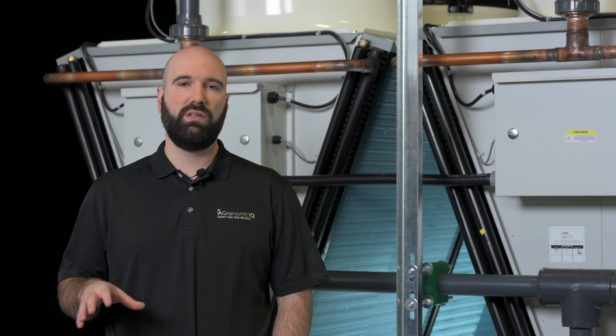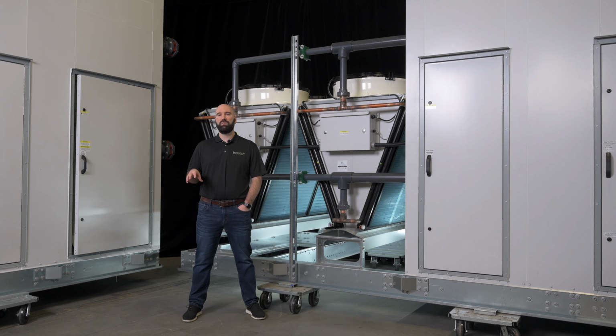Here I am in front of the dry cooler section of this 55-ton piece of equipment. And this is a packaged unit, which means that the dry cooler is attached to the system, factory filled, ready to go from us. And so there's no site work that needs to be done to get cooling working on this equipment. We're using a dry cooler and a water glycol mix for our heat rejection for 2 reasons. And one is it allows us very fine control between outdoor heat rejection through the dry cooler and the reheat. And again, we talked about the hydronic reheat loop earlier when we were talking about the pod section.